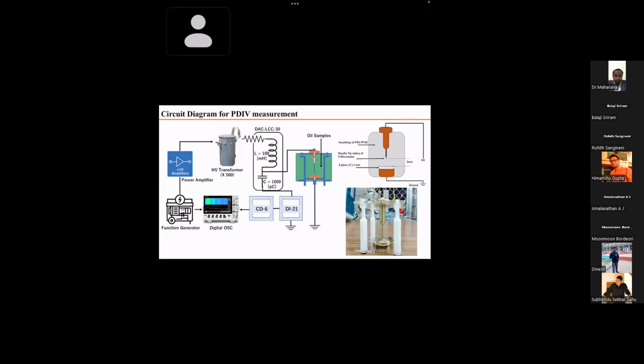So would the design stress change depending on what oil you use? I'm asking whether there is a difference in design stress between ester oil and mineral oil. We have to agree there is a difference in design stress between ester oil and mineral oil. So will it be higher or lower, sir? Design stress will also be higher. In the case of ester oil, it will be a little higher.